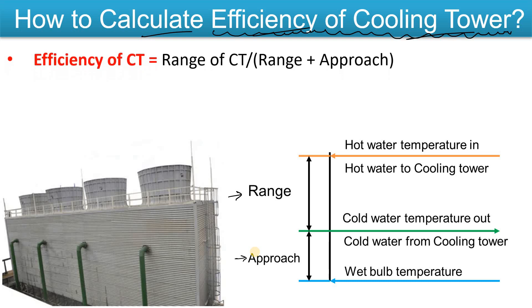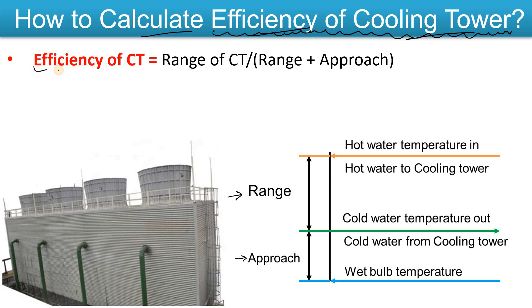The efficiency of the cooling tower depends on the range and approach. Simply, the efficiency of the cooling tower is the range of the cooling tower divided by range plus approach. There is nothing like rocket science when we calculate the efficiency of the cooling tower — it is only range divided by range plus approach.